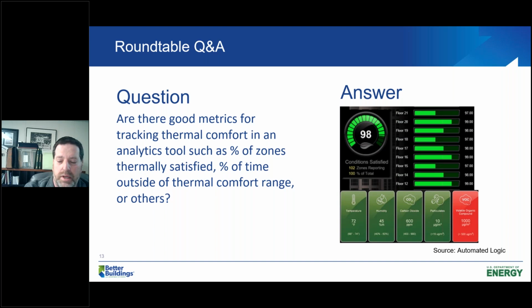Carbon dioxide is another one. This is showing 600 parts per million. In this specific example, they have a range of 400 to 900 parts per million. There are other ones out there for particulates and VOCs as well. So those are available, and as indoor air quality and healthy buildings become more important, there are more things available. As long as you have the sensors, you can add them all up and get an overall score for indoor air quality. Yeah, and obviously with pandemic mode operations, that's becoming more important, as CO2 can be a proxy for the indoor air quality in your space.